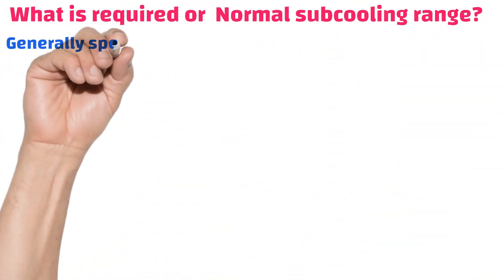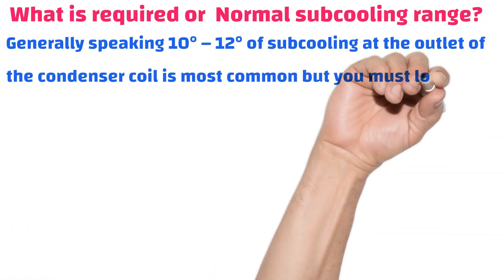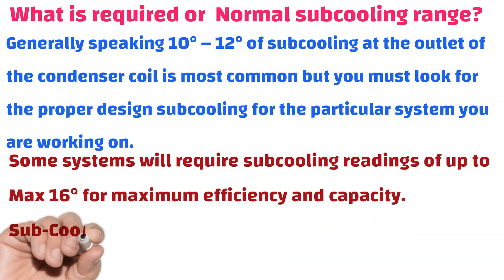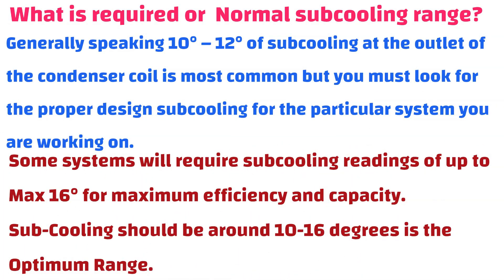The normal sub-cooling range: generally, 10 to 12 degrees of sub-cooling at the outlet of the condenser coil is most common, but you must look for the proper design sub-cooling for the particular system you are working on. Some systems will require sub-cooling readings of up to 16 degrees for maximum efficiency and capacity. Sub-cooling should be around 10 to 16 degrees as the optimum range.